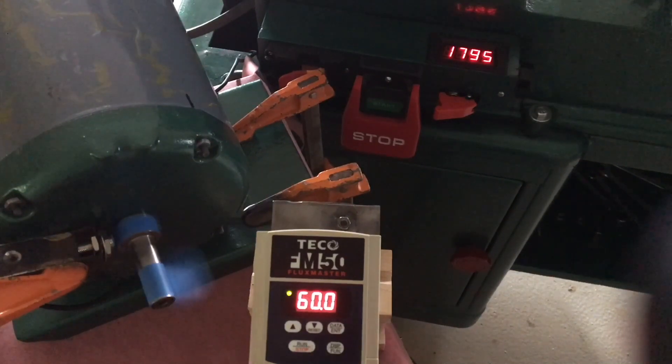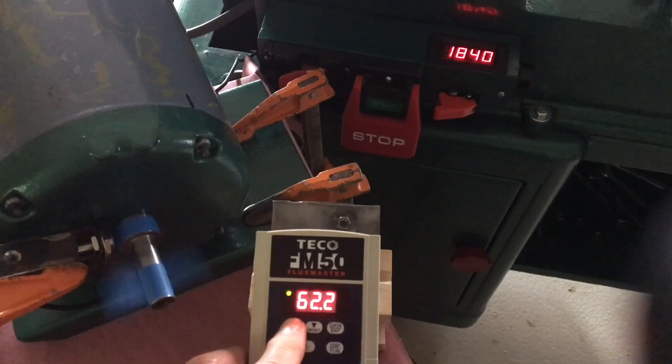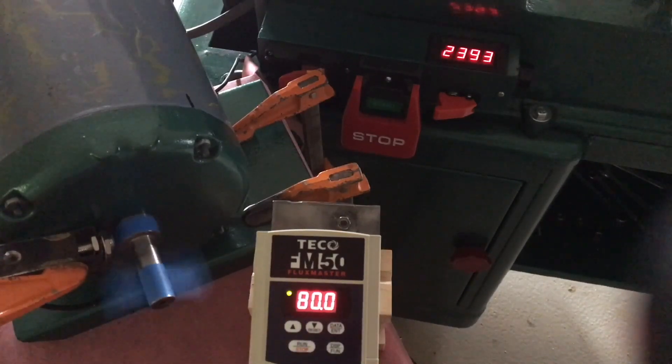So here we are at 60 hertz again, 1800 RPMs on the motor. Now I'm just running it up to the maximum that I've got set, which is 80 hertz. And now you can see it's almost 2400 RPMs on the motor.